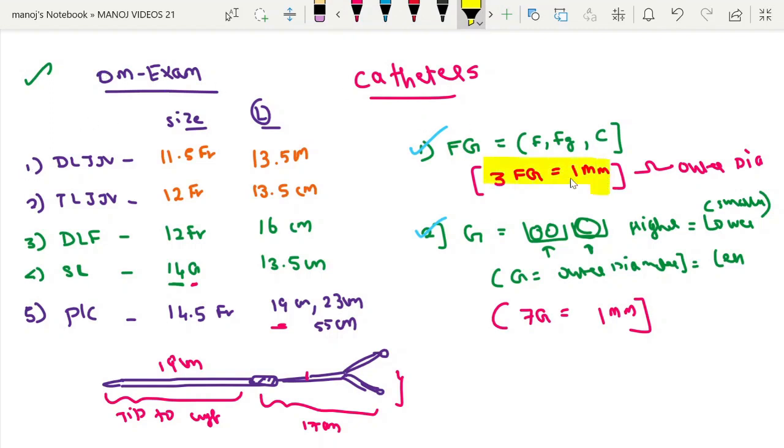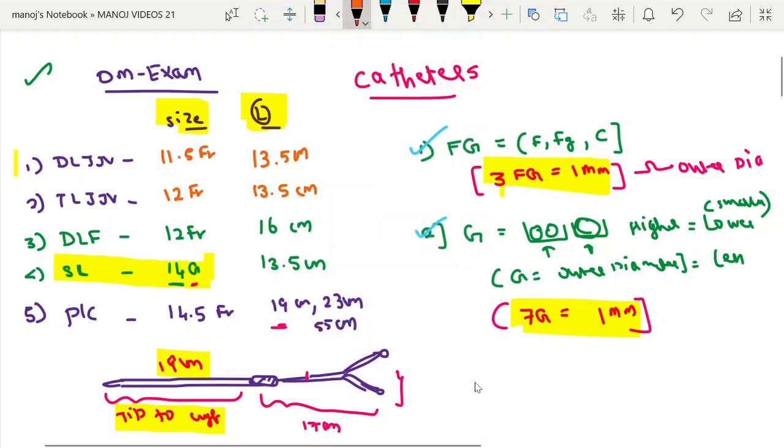Summary is: 3 French is equal to 1 mm, 7 gauge is equal to 1 mm. The IJV catheters and the straight catheters, size is mentioned over here, length is over here. Except that single lumen catheter which is being mentioned in gauge term, rest are being measured in French gauge only. For perm cath, 3 lengths are available: 19 cm, 23 cm and 55 cm. That is the tip to cuff. So this is the summary of the catheters.